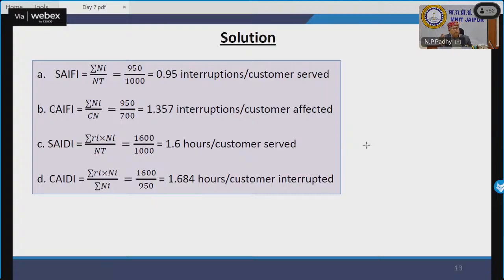Tell me, in this SAIFI data, does 0.95 mean every 100 customers, only 5 are getting full supply? 0.95 interruptions per customer served - that means it is not talking about 95 out of 100. It is giving you an index, information about interruption per customer in the whole system. This example we have taken is a very, very worst case scenario, in this case it shows 95% of people are getting affected. Are you clear? But practically it could even be 0.0095, because that's just a numerical exercise - this is helping you calculate easily, but it could give a wrong impression. It is true, though, that most of the customers actually got interrupted because out of 1,000, 950 got affected.